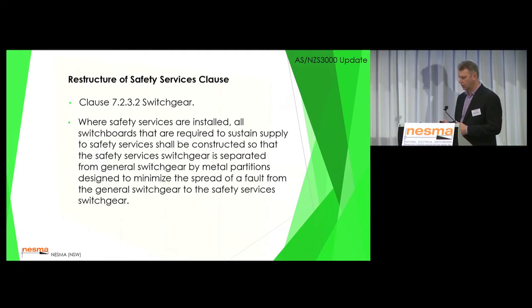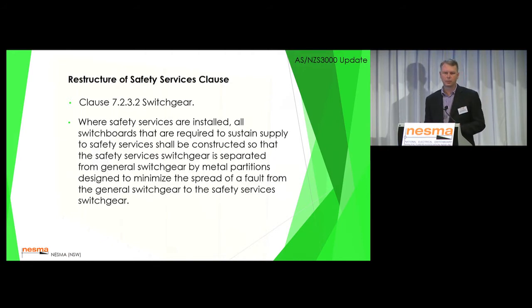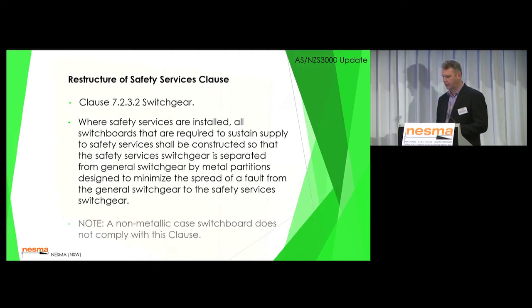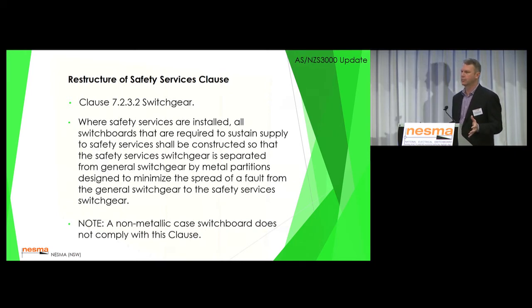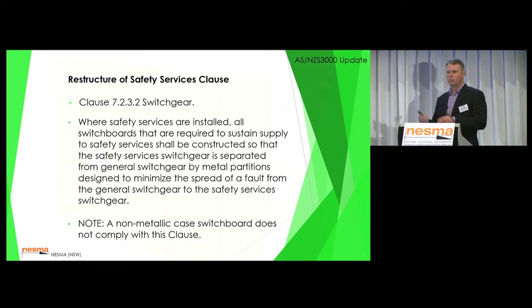Now, one of the things that used to be possible is that you could provide separation that wasn't with metal partitions. They've clarified this now. A non-metallic case of a switchboard does not comply. Now, you might see some smaller assemblies that had a lift circuit effectively off a distribution board, and you might have wanted to put that into some kind of polycarbonate centre to separate that. That's no longer permitted. It must be its own section.